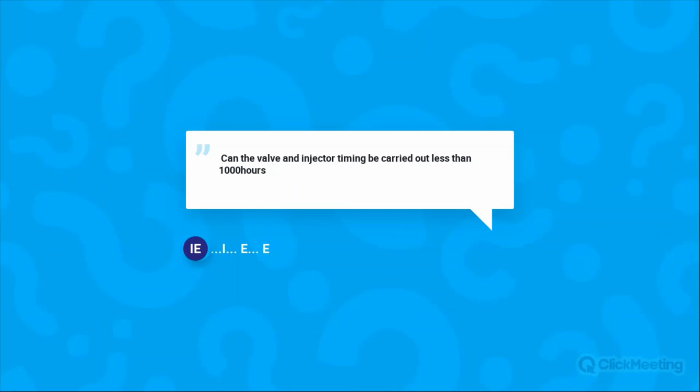If one is okay, it means the others are probably fine, so go fast through the others with the feeler gauge that you have. If they are all okay, forget it. Do not do the adjustment, because sometimes the engine will run 2,000, 3,000, or 4,000 running hours before you find out that the adjustments have changed and you need to readjust again. So double check. If you find more than one piston okay, you don't have to do this at 1,000 running hours. Just skip it.